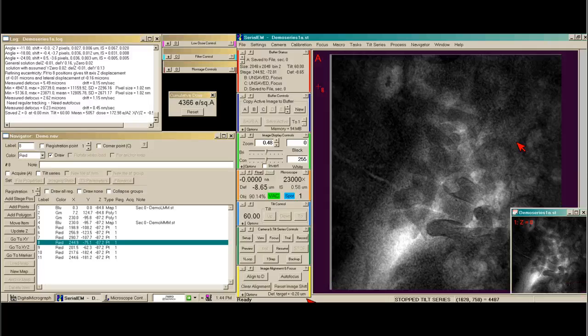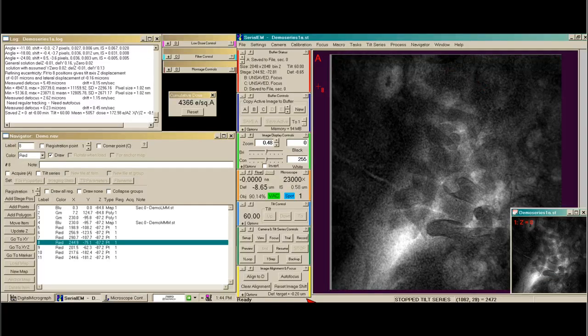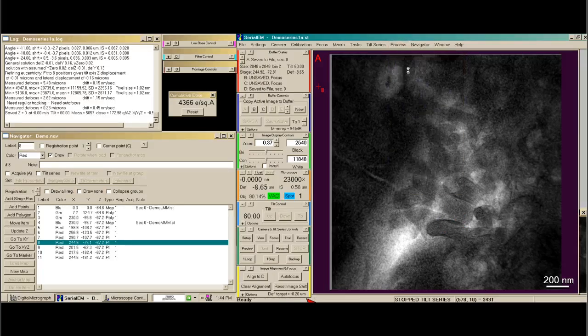I have a mini tilt series collecting in this small box so that you can always movie through this and see all the images and know if anything funny is happening. Also, you'll see that we have a focus gradient — this part of the image is in focus, this is over-focused, and this is under-focused. This is perfectly normal in tilt series acquisition and not a problem because at high tilt, only the center third of your image is in your tomogram anyway. I look to see if the image is nice and crisp with no drift, and this looks really great. If you wanted to check, you could say process FFT on this image and you would see that we have no drift, that we have a nice round circle.